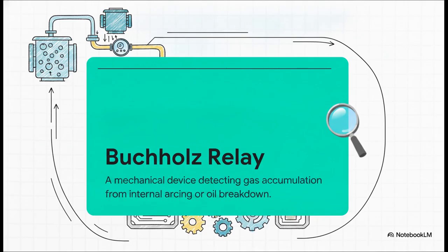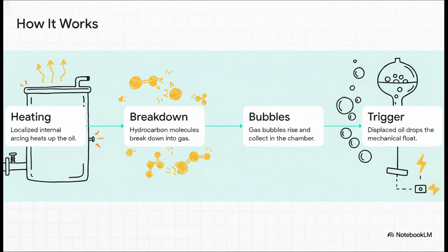Now, since gas is naturally lighter than oil, any gas generated inside the main tank is going to want to rise, right? And its only path upward goes directly through the Buchholz relay. It is brilliantly simple how this works. First, that localized internal arcing heats up the oil. Second, that intense heat actually breaks down the hydrocarbon molecules in the oil, literally generating gas. Third, those gas bubbles float up the pipe and pool in the top chamber of the relay. And finally, as that gas fills the chamber, it pushes the oil out, making the oil level drop. When that happens, a mechanical float switch inside the chamber just drops right along with it. We've literally just translated an electrical failure into a pure physical movement.